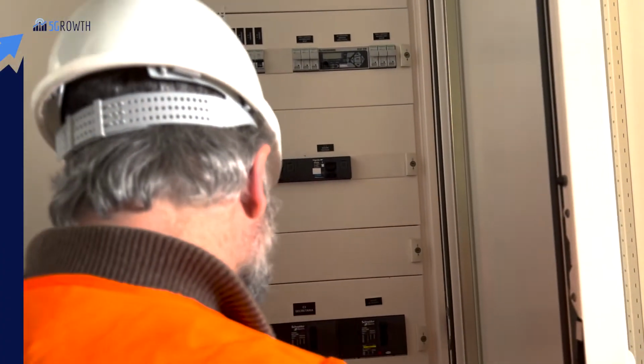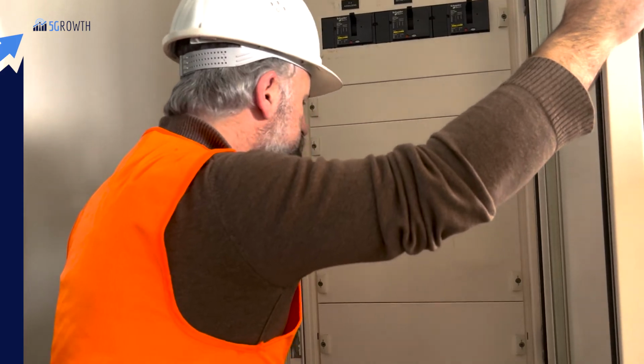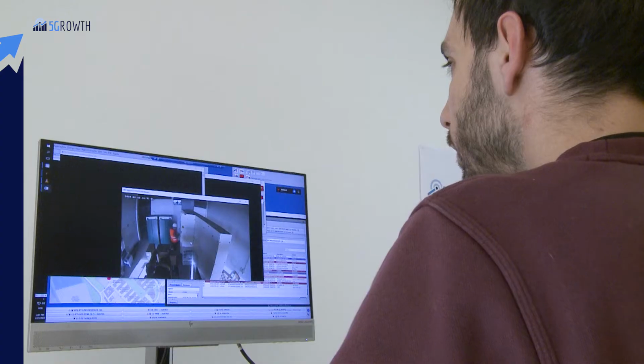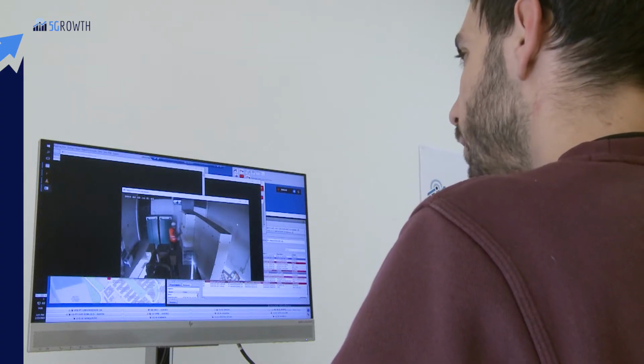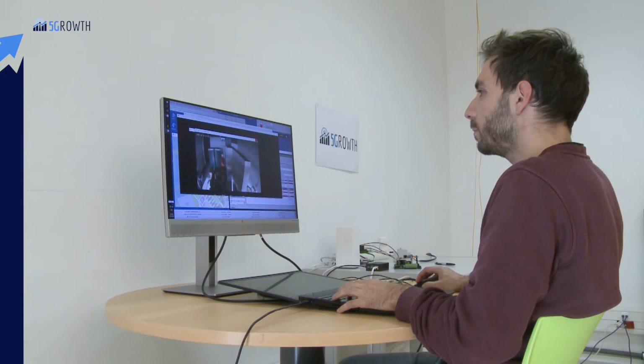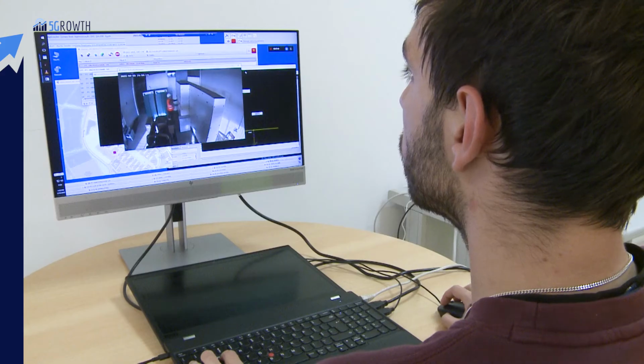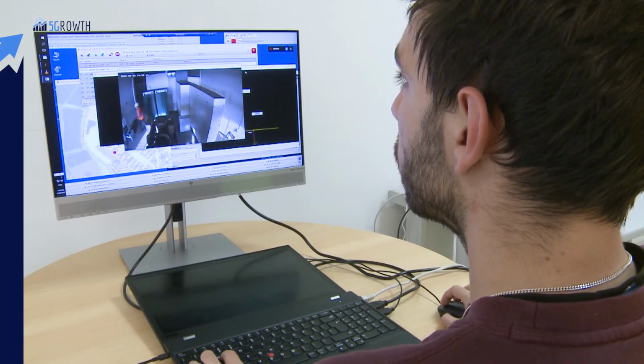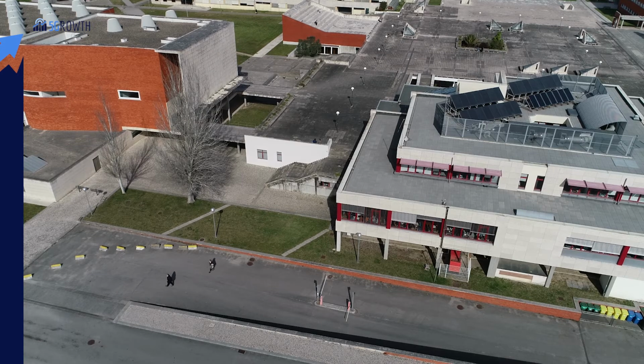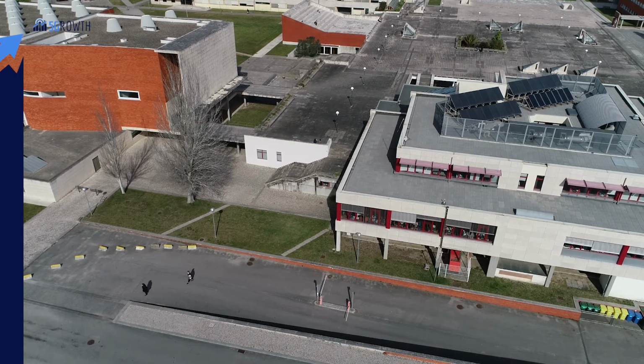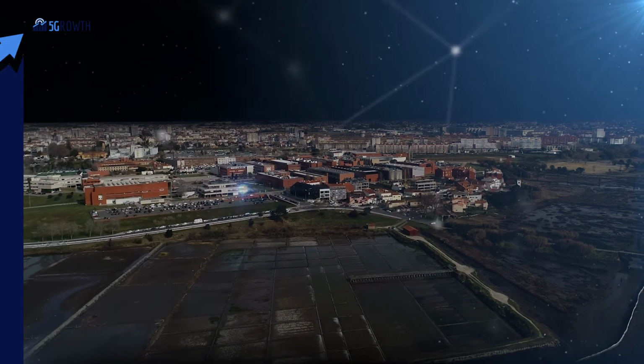Through the video streaming, the operator can follow the field crew actions while they investigate the root cause of the incident. This enhanced supervision of the secondary substation would not be possible with the communication technology currently deployed in the distribution network across the secondary substations. We are talking most commonly about GPRS, with very low throughput capabilities and higher latency than required for real-time remote operation.